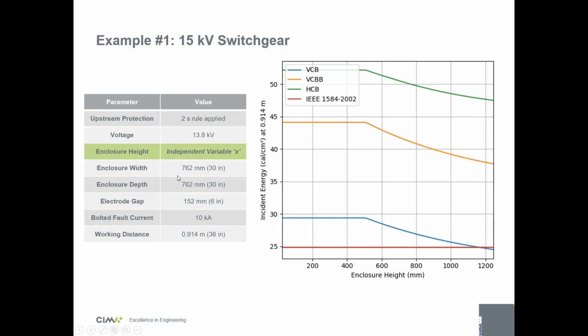Now let's fix the voltage back to 13.8 kV and vary the height. What's the impact of the height? You see the worst case energy is always when your height is smaller. When your height goes up, your energy goes down. If you look at the curve of the 2002 version, it's flat, because height is not a parameter in that equation. The other ones vary, but not by much. The VCBB, for example, starts at 44 and then drops to 38. It's not a significant drop.